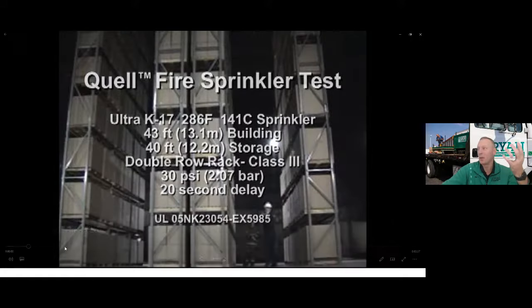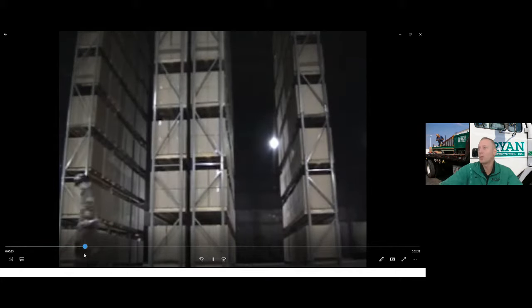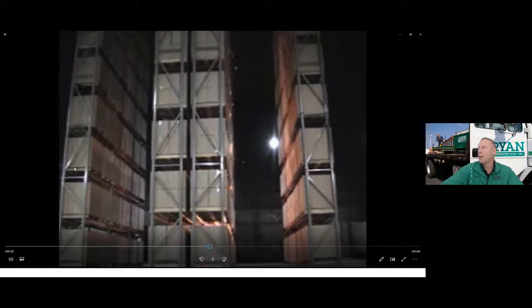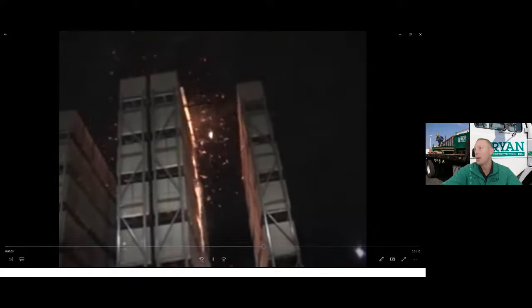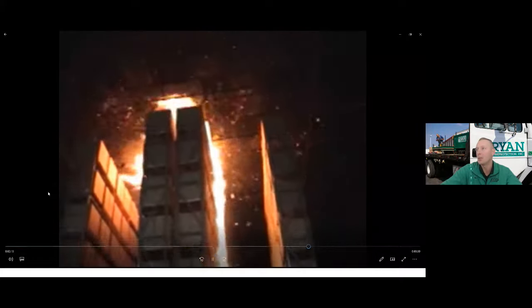This is a fun video showing a fire test of a 40-foot storage wet-type sprinkler system. It shows a time lapse of a fire starting and how it grows within rack storage containing cardboard and wooden pallets, and how fast it reaches the ceiling deck. We're only about two minutes in to the fire starting at the lowest level. Before long, the sprinkler system activates and you can see the impact it makes. The point of showing this is that without the correct sprinkler system, this facility likely would not have been able to contain the fire, which could lead to catastrophic loss in a large warehouse full of this type of commodity and storage arrangement.